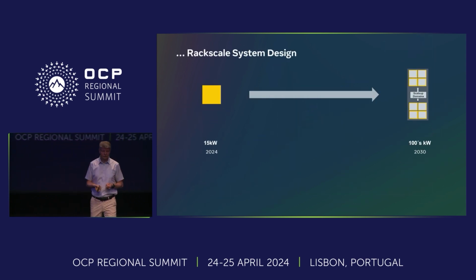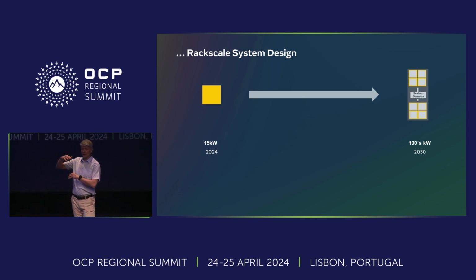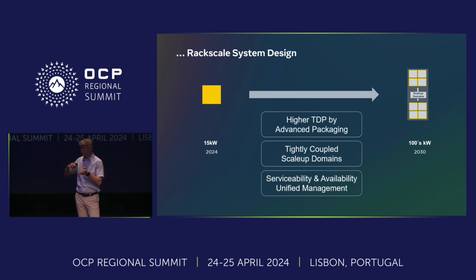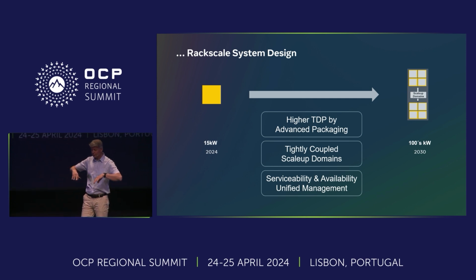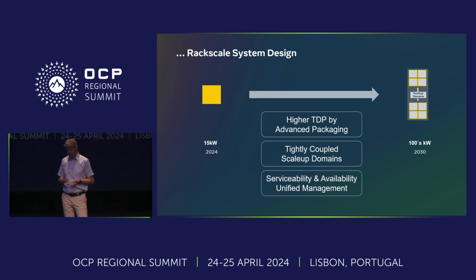This also drives or impacts the rack scale system design. The Grand Teton systems we use today, we typically pack 2 of those into a rack, so that's 16 GPUs within a rack, roughly 15, 16 kilowatt. As we move to the next generation of systems, the power density will continue to increase, getting into 50, 100, and several hundred kilowatt racks that demand liquid cooling. This is again driven by higher TDP through advanced packaging and tightly coupled scale-up domains.